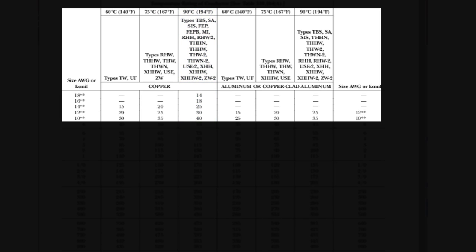The reason why we often say that is because we're often talking about NM cable, which is non-metallic cable, otherwise known as the trade name Romex. This is the typical wiring that's used in a lot of modern houses, and NM cable ampacities have to stick with 60 degree Celsius. The basic residential wiring in a normal house for the lights and outlets with NM, which is Romex, is rated at 30 amps for number 10 wire, 40 amps for number 8, 55 for number 6, and so on and so forth.